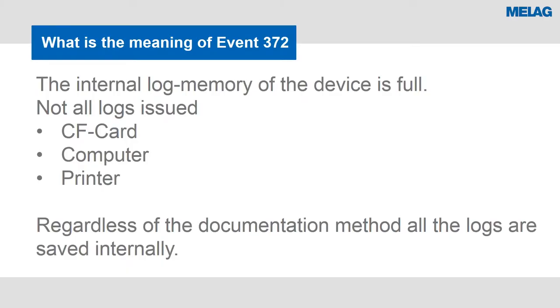What is the meaning of event 372 for you and your device? It means that the internal log memory of the device is full and not all logs were issued. You have several possibilities to issue the log files to the output media of your desire: the CF card, the computer, or the printer.